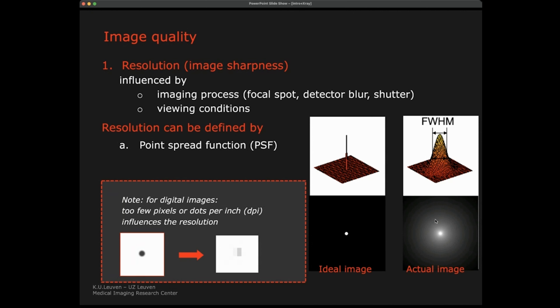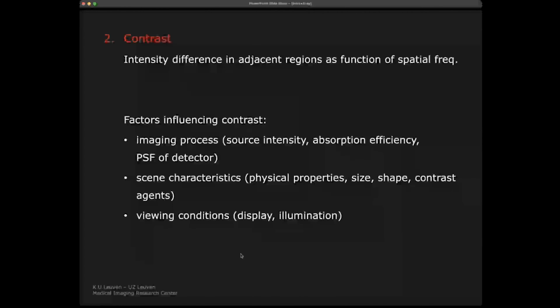What is important is the full width at half maximum — what is the smallest object we can see and how does it appear? One phenomenon is partial volume effects: if we have a very small tumor, its information can be spread over different pixels, so the intensity can go down. Because of the size of an object, its apparent intensity in the image can also be different. These are things to keep in mind.